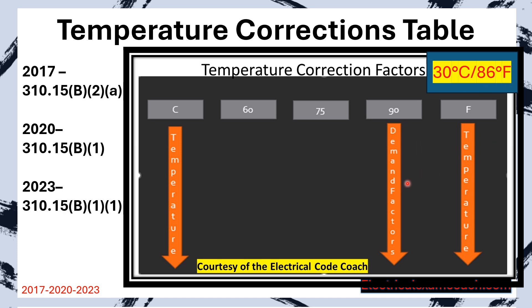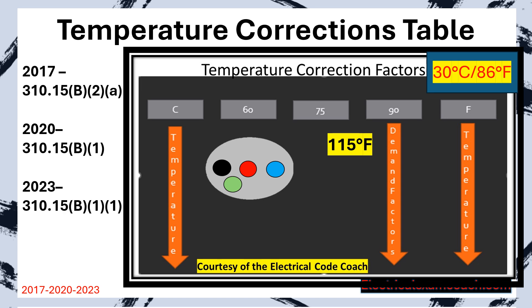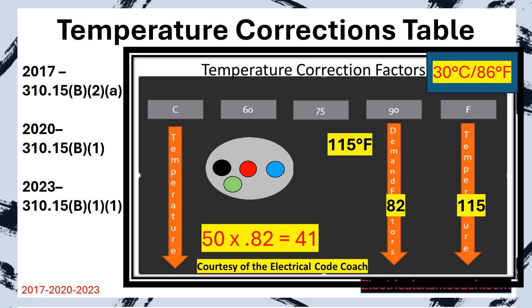Let me give you an example. Imagine we have a circuit with black, red, and blue conductors plus an equipment grounding conductor, in an ambient temperature of 115 degrees Fahrenheit. We start on the right-hand side, find 115 degrees, then come over to the 90 degrees C column and find our correction factor — it's just another demand factor. If a wire was 50 amps before, and the correction factor is 0.82, we take 50 times 0.82 and get a new allowable ampacity of 41 amps.